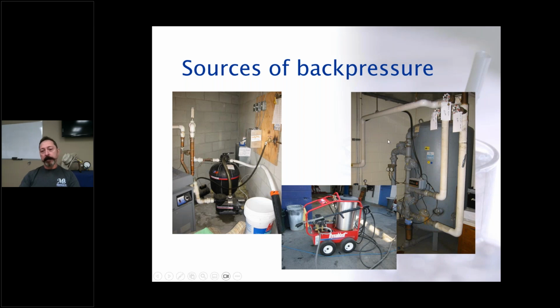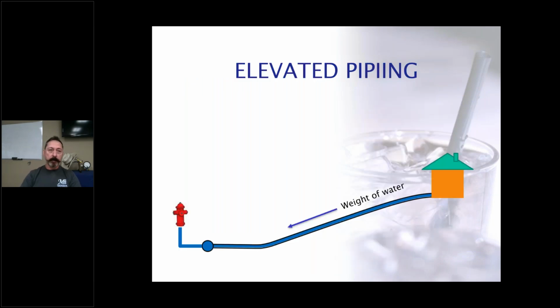So there are heating systems, pressure pumps, or car washes with lots of pressure, situations with higher pressure than the distribution system. These are the types of things that can show up in any utility that has those types of systems. And elevation, in BC here and other parts of the world, if your distribution system is on different elevations and you're supplying to different plateaus, the weight of that water can also have an impact. Should you lose pressure, that water can drain back into your system due to its weight.